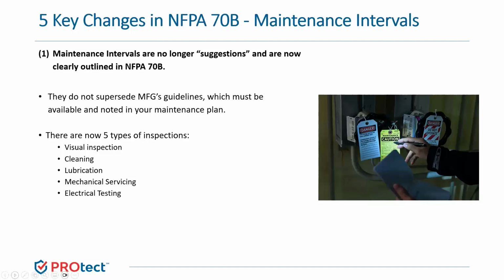The maintenance intervals listed include multiple types of inspections: visual inspections, cleaning, lubrication, mechanical servicing, and electrical testing. So you're not just looking at your annual IR inspections that you traditionally complete. Now you have 5 types of inspections that must be managed, and they don't always have the same maintenance intervals. So not only must you manage each component type and each inspection type, but you also must allow time necessary for corrective actions, repairs, and any deficiency management identified through those inspections.